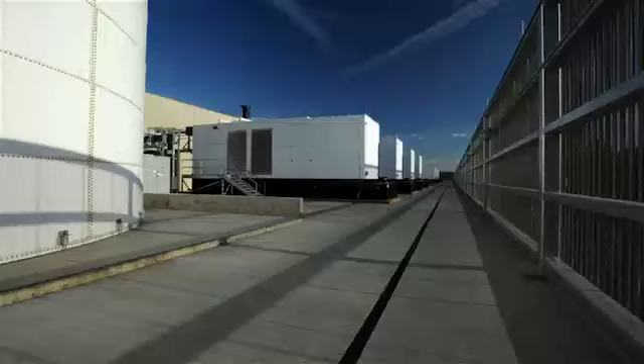We cool the space as well from the data hall, so that heat from the electrical room then returns back into the same plenum space that we draw the heat out of the data hall, then up to the penthouse. Our generator yard, rather simple. We installed the generators on belly tanks, which minimizes the amount of piping that's required. You don't have to worry about a manifolded system. The generator draws whatever fuel it requires from its own tank.